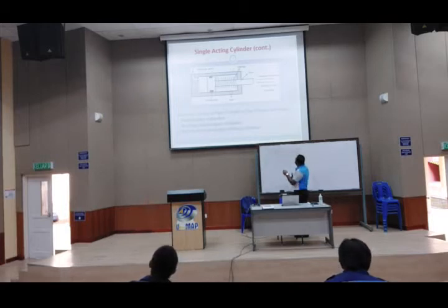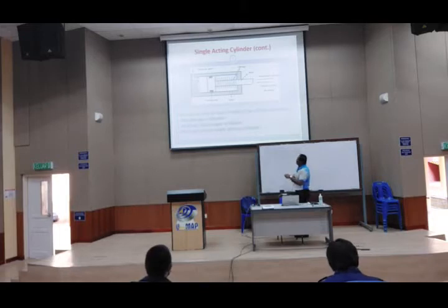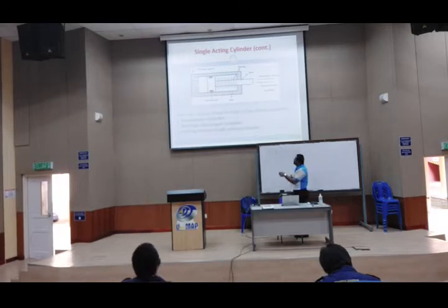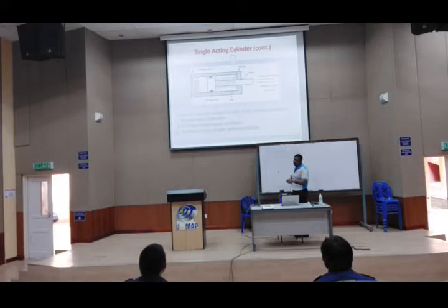Okay, then you can have an extension. So based on this, when the compressed air enters, the cylinder will start to extend. So extension is based on compressed air and return by spring. If the compressed air goes out, automatically the spring will take over. It will go back to the original position.